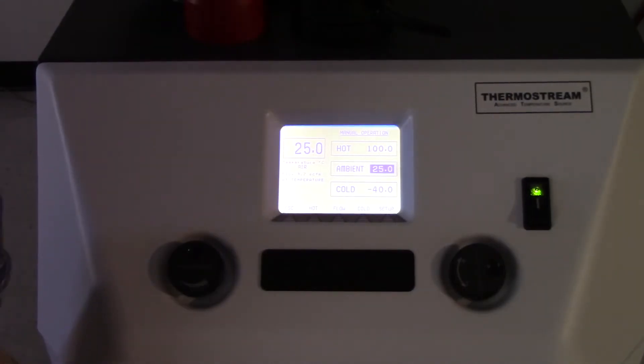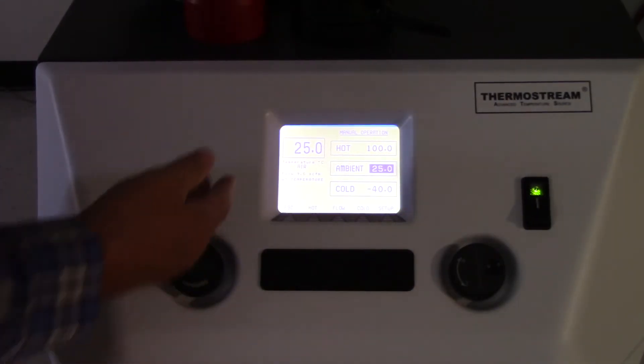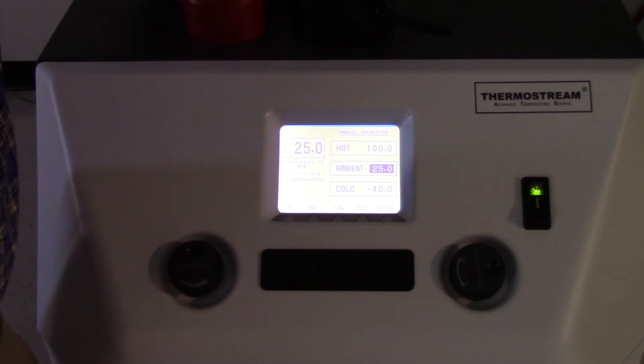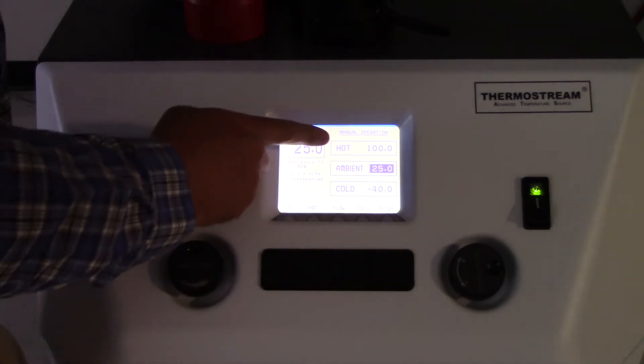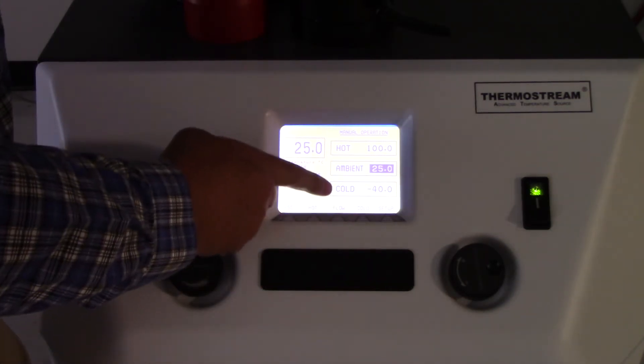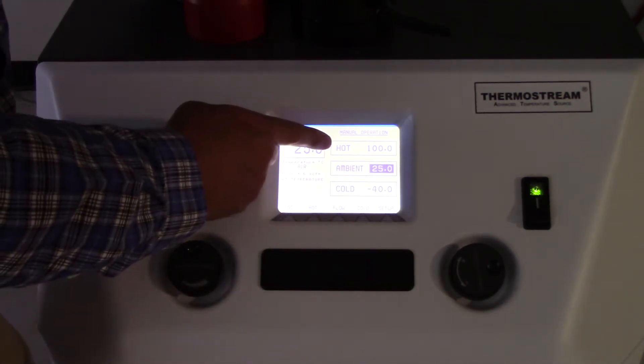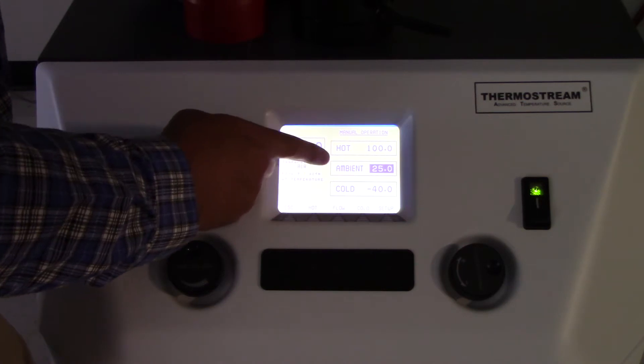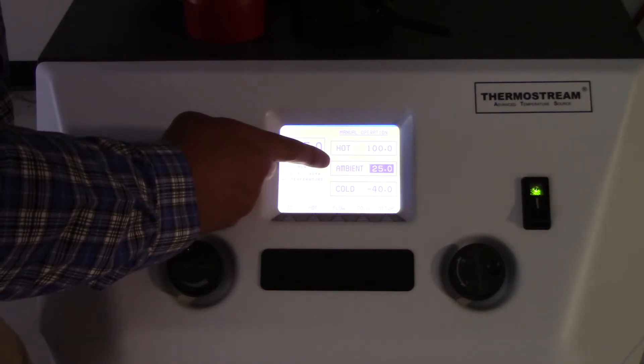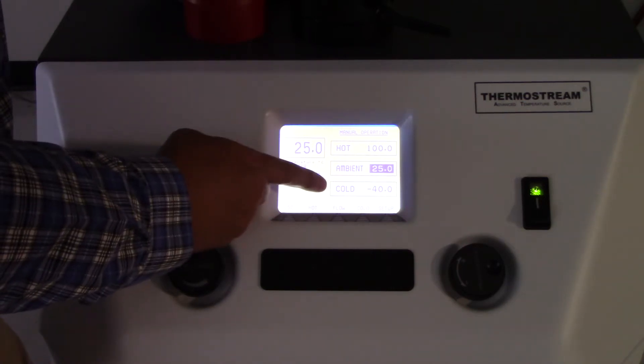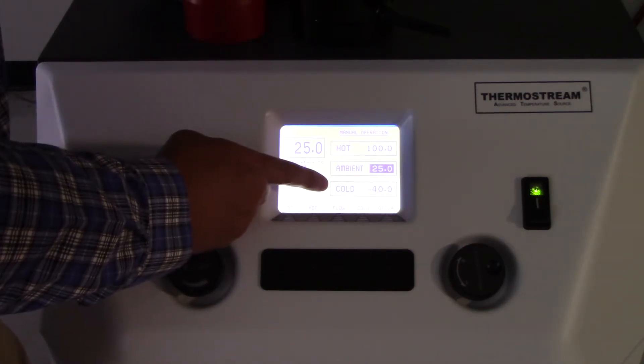As far as the user interface is concerned, this is the manual operation, and you can see that you've got three temperatures defined here: a hot temperature of 100°C, ambient at 25°C, and cold at -40°C.